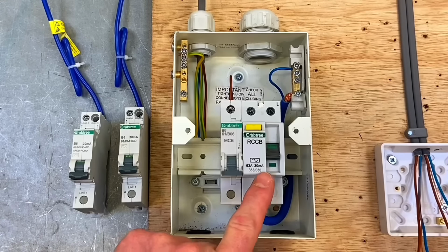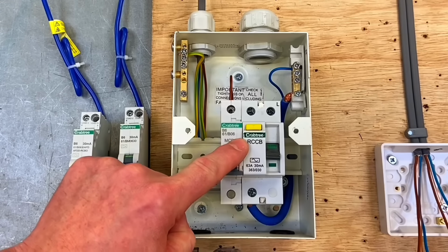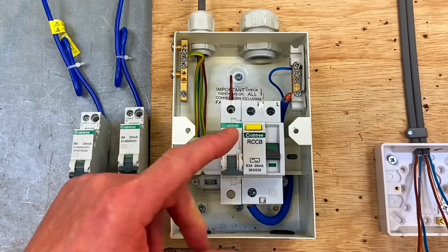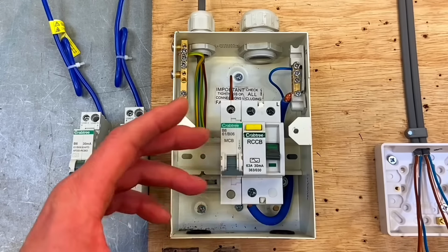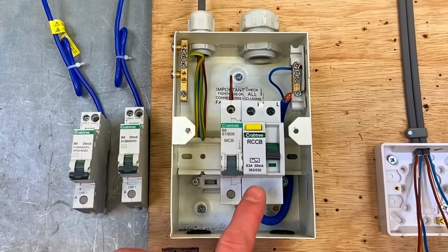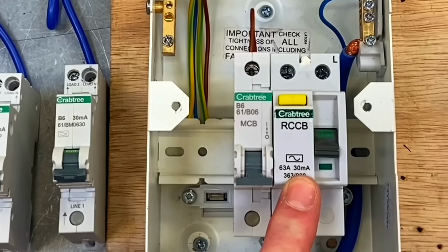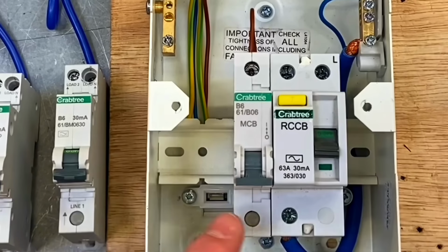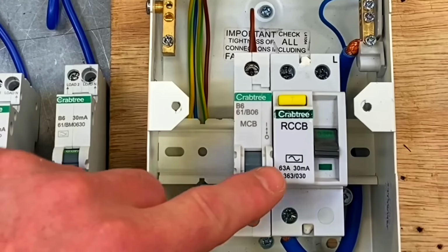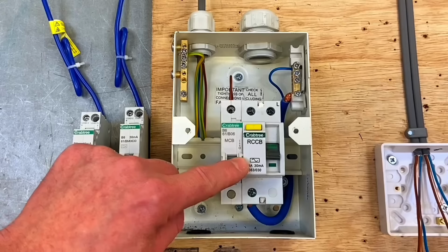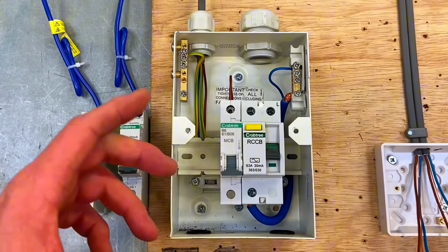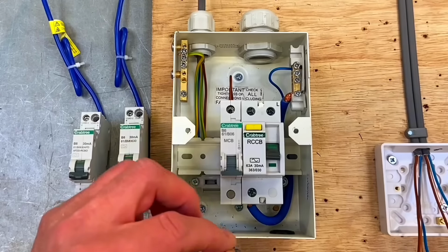We've got our RCD protection in the form of an RCCB, because we know that all domestic lighting circuits need additional protection by an RCD, rated at, in this case, 30 milliamps or less. So that bit's correct. However, my students will notice that we've got the AC waveform, and we're aware that we are not massive fans of AC RCDs.